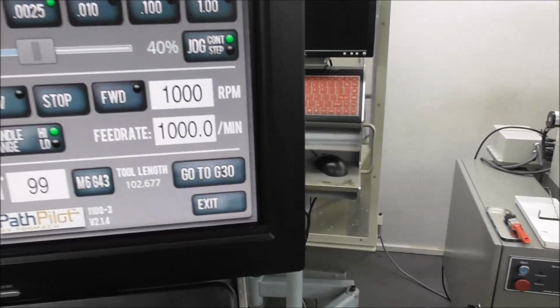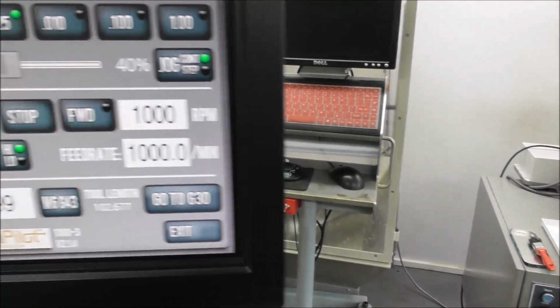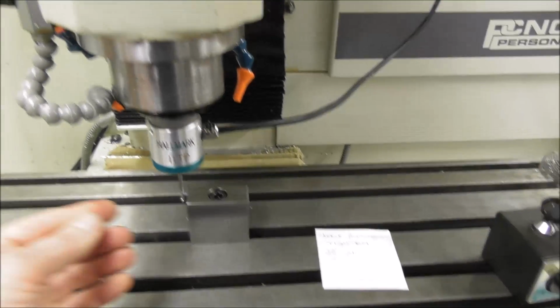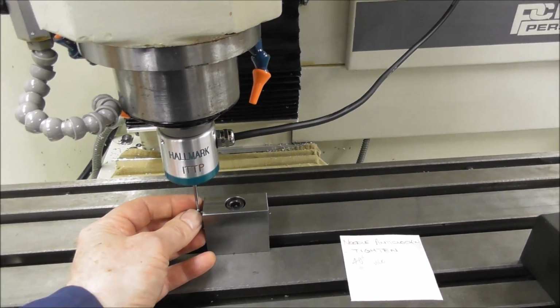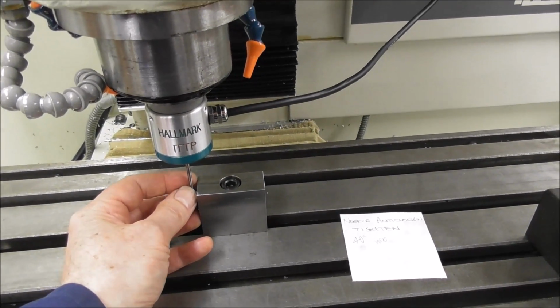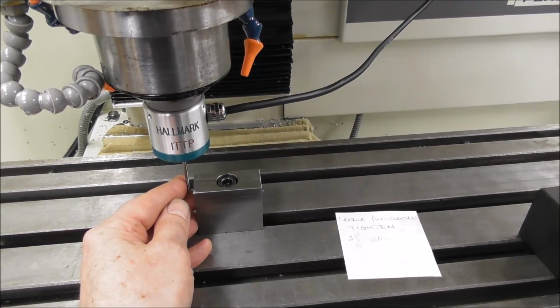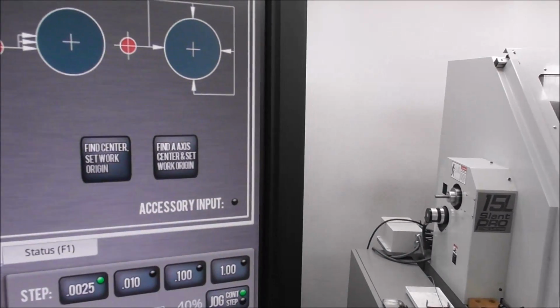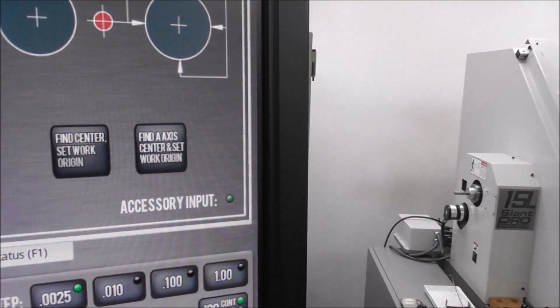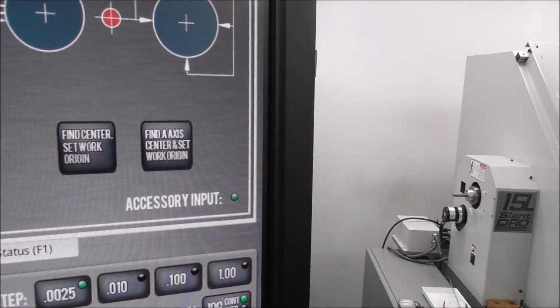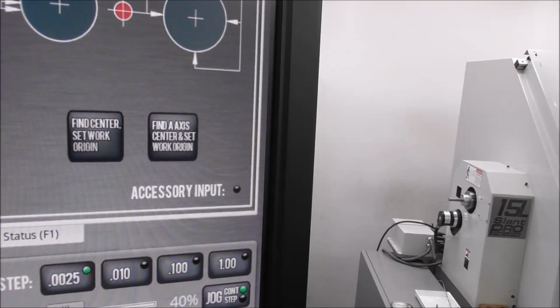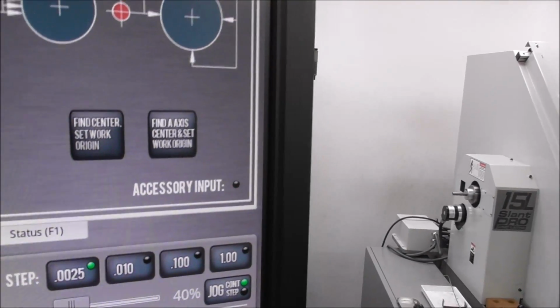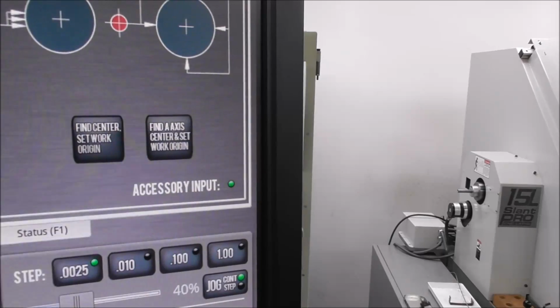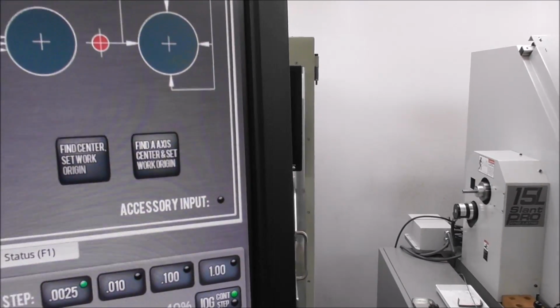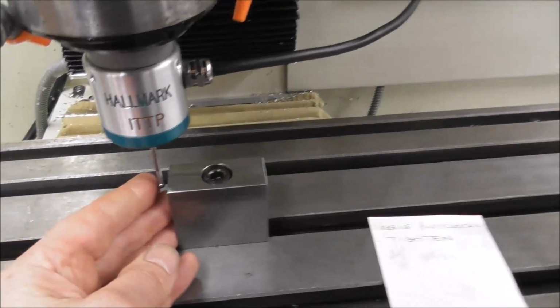Let's switch it now to the probe page. Okay, so we're going to do a quick check now. If you put your finger on the stylus tip so that you can move the stylus and have a look at the accessory input indicator, you can see when you move the stylus tip, the indicator light comes on. That's registering that everything's working, and you can check it in every direction and make sure that it comes on and off. Let's just go through that again.